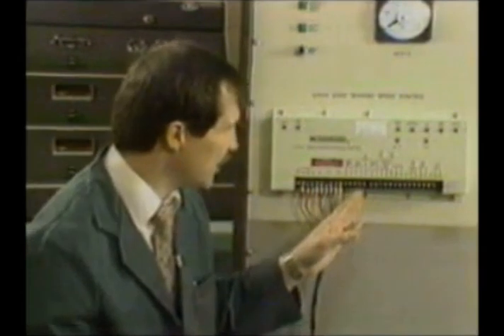We show just a contact here. You can also, on page 8 of the manual, it points out to you how you can put an isoch droop switch in line with that circuit breaker auxiliary contact. So if you do want to run two engines in droop against the utility, you may. You won't always go in isochronous. And then the one other thing I need to point out about terminal 14 is if no voltage is on terminal 14 and you're in droop, if the droop pot is turned fully counterclockwise, you're calling for 0% droop, which is the same as running in isochronous. So if you keep your droop pot turned fully counterclockwise, you will be running in isochronous.